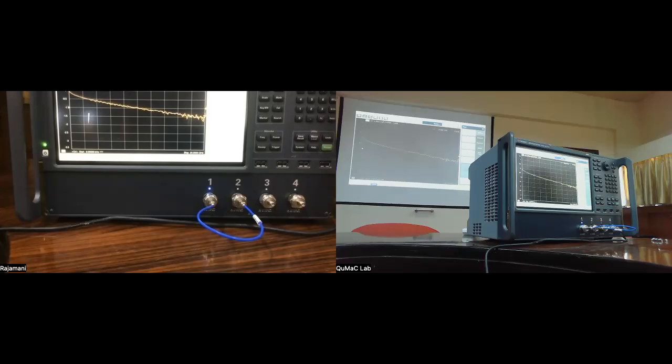Okay. You have to worry about the kind of mismatch we saw yesterday. That was just something seriously wrong. They're both coming from the same problem, except that there it was just horribly miscalibrated. And this is because the electronics inside has to be calibrated to know what power level corresponds to what. So this is a procedure which needs to happen.